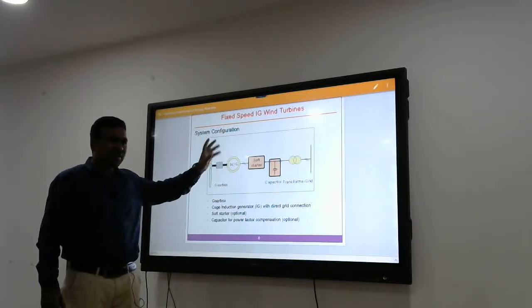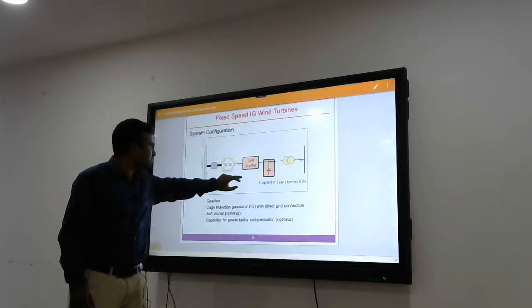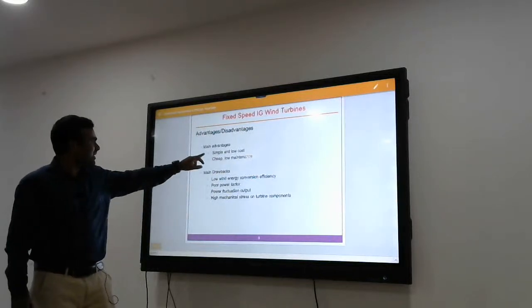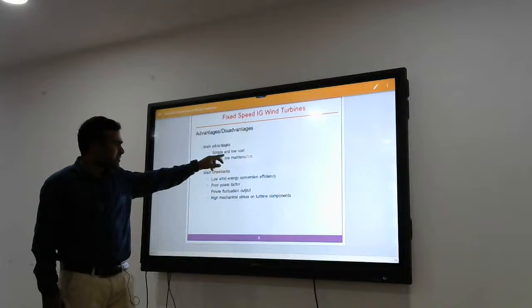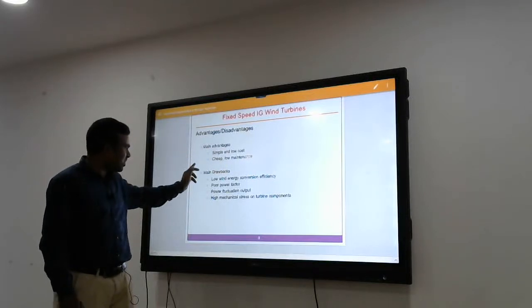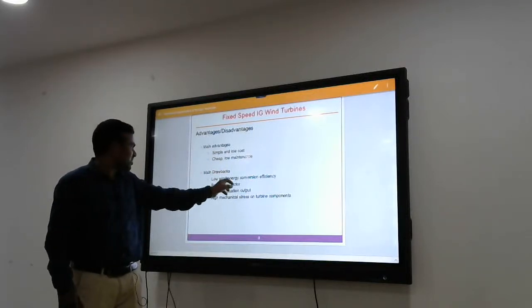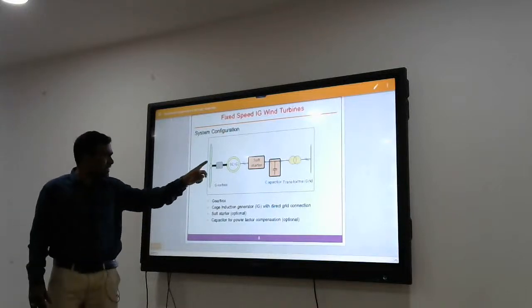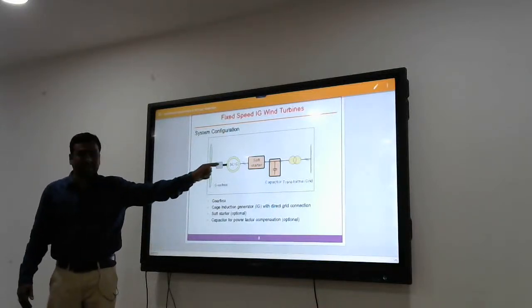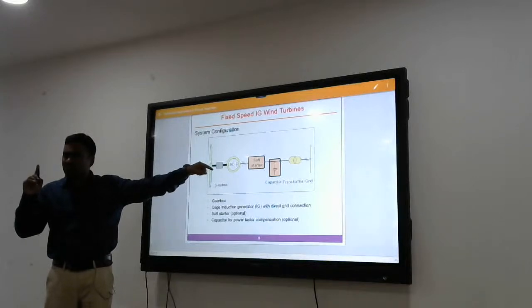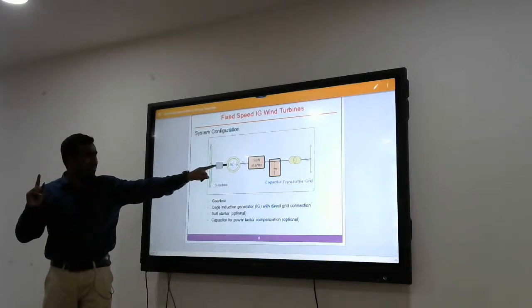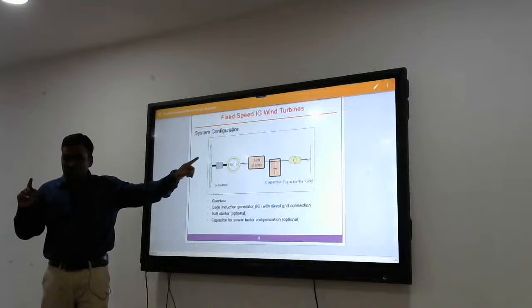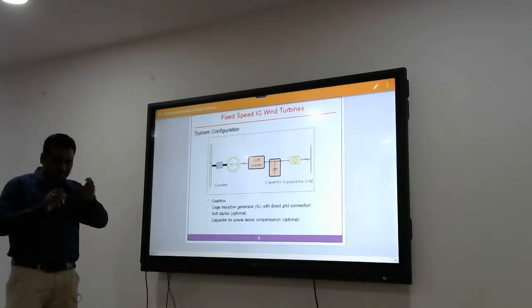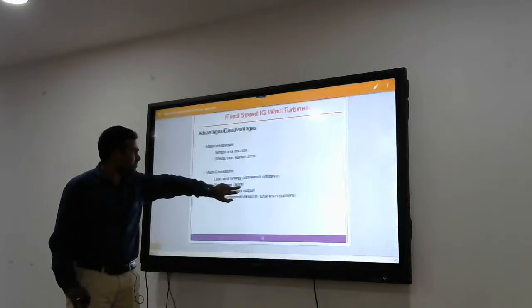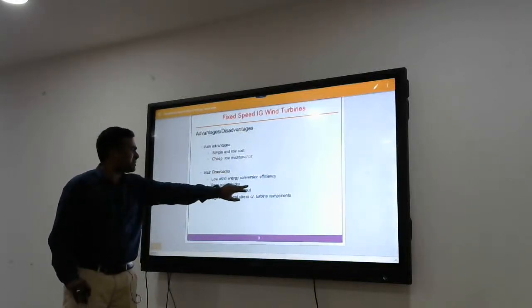So most of the older installations are this fixed speed type. The advantages: simple and low cost, cheap and low maintenance. But the main problem is mechanical stress, because even if your wind speed is changing always, you have to run at a particular fixed speed always. That too, you are depending on this gearbox and this pitch angle. So you have so much mechanical stress. You have to change the speed. And power factor is the problem.